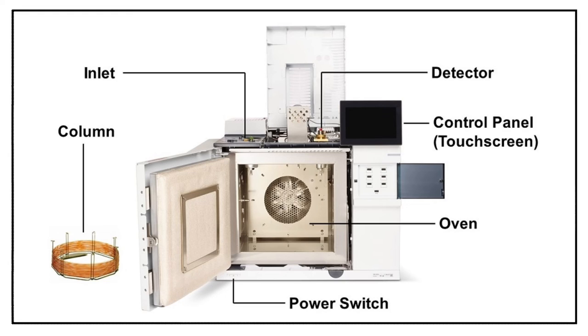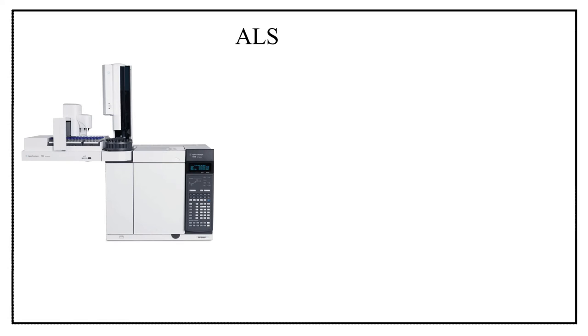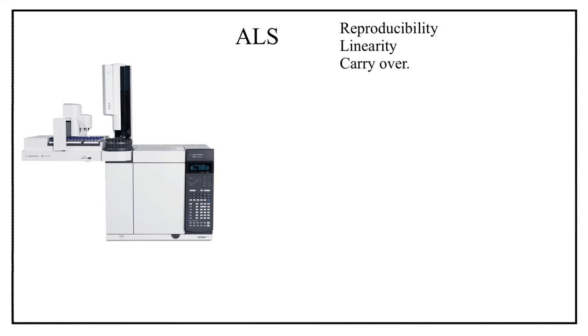Let us now know about all the calibration parameters one by one. Firstly, ALS — Automatic Liquid Sampler — is calibrated with the help of three calibration parameters: reproducibility, linearity, and carryover. Now comes the HSS, which means Headspace Sampler, and HSS is calibrated with the help of four calibration parameters.